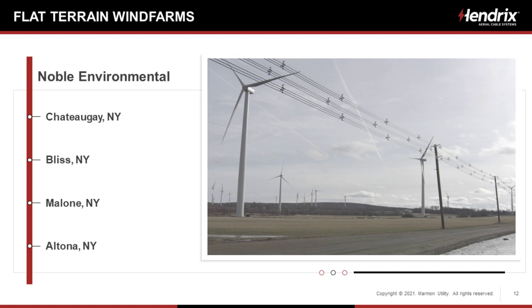So I'm talking about ridgeline wind farms, which is the majority of the wind farm applications that call for spacer cable. But we also have several flat terrain wind farms. Here's a series of projects we did with a company called Noble Environmental, and these are four wind farms scattered over, oddly enough, four counties. So most of the strings here, from those individual turbines to the collector circuits, most of those strings were underground cable. Some of them were spacer cable. 100% of the collection circuits were spacer cable.